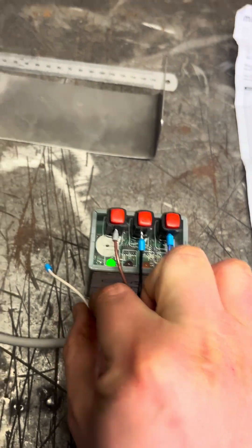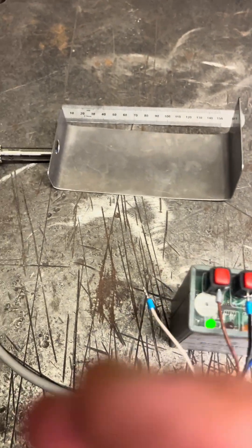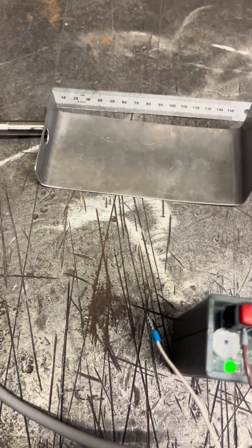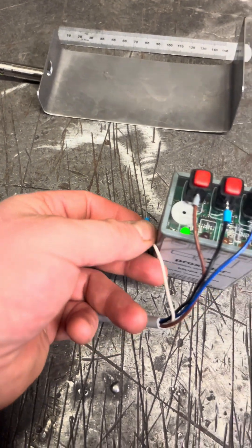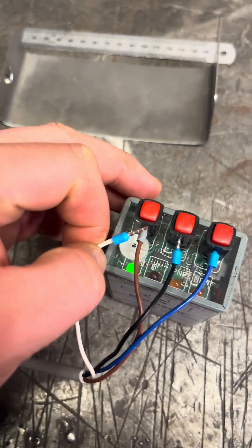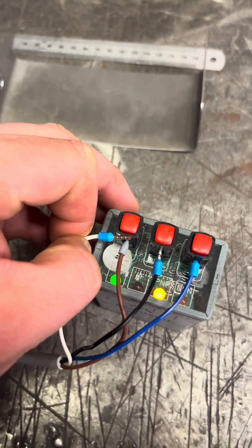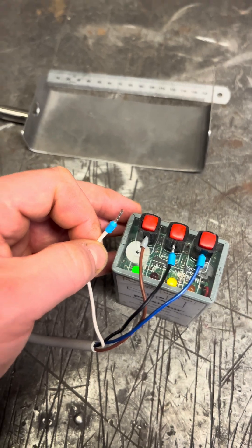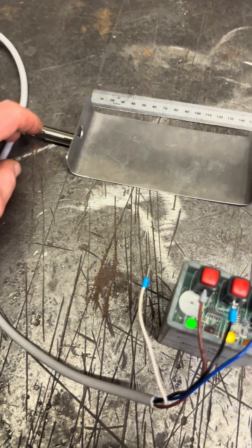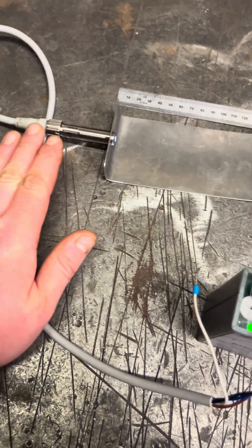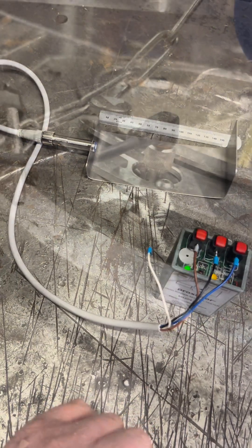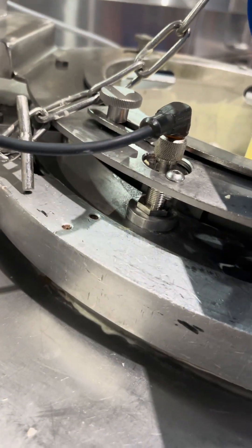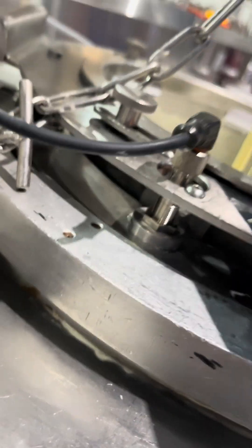And then with that set to the 150 mil on our little jig, then you take your teach button and you put that on your positive for three seconds. Off, that'll be flashing yellow and green, and you dab it back on. Because what you're doing then is you're telling the ultrasonic sensor the time frame that it needs to have. So now with the level sensor on the machine itself, I'm going to show you how I would test it.